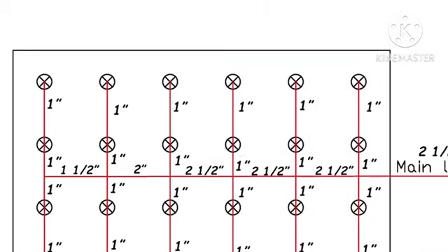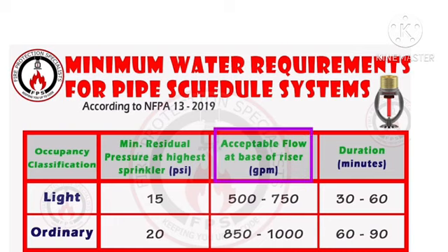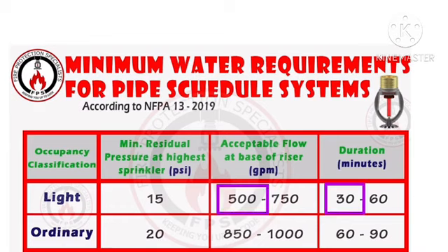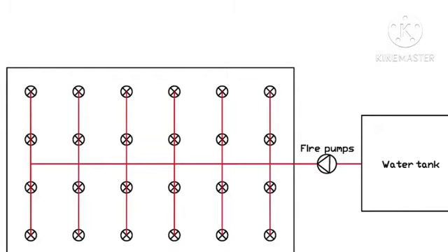Now, what are the minimum water supply requirements for pipe schedule systems? The table below summarizes the minimum water flow rate, residual pressure, and duration of pipe schedule systems. Therefore, 500 GPM multiplied by 30 minutes means a minimum of 15,000 gallons water tank shall be constructed.